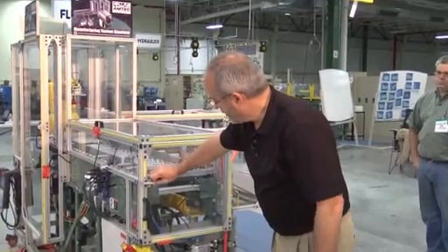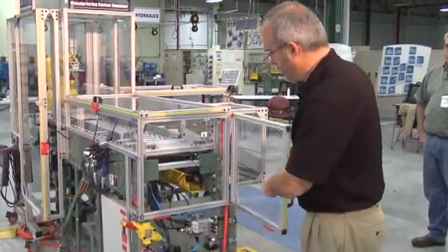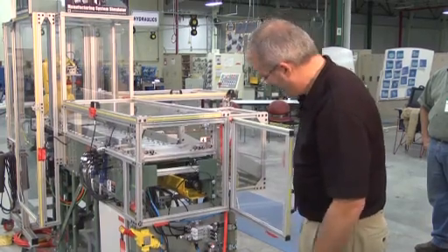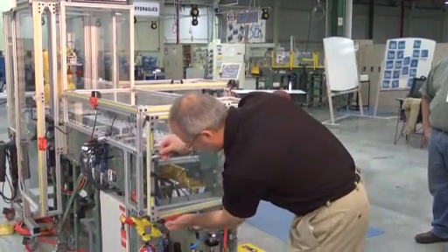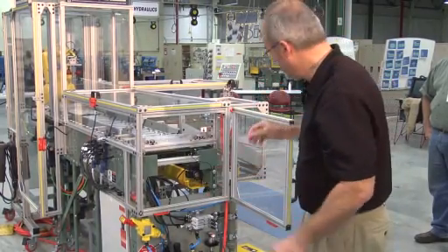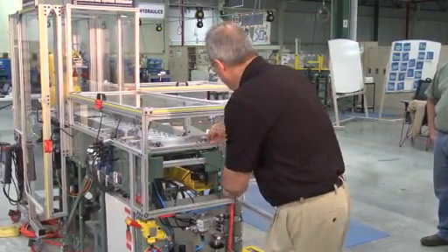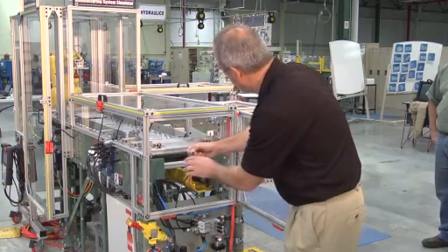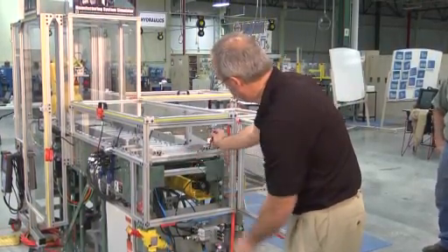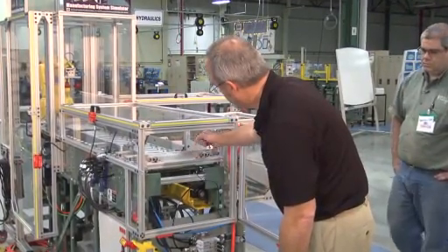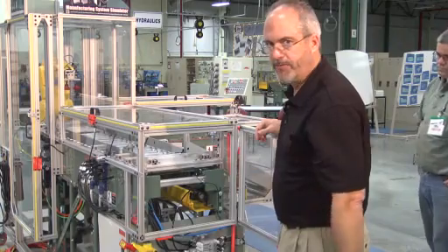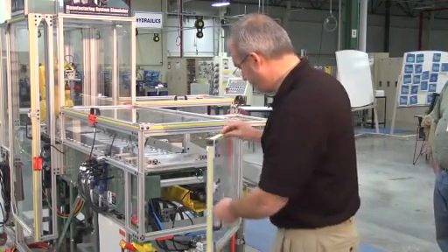Just like we had on the servo drive, and incidentally that was a demonstration here of another Estop. We have the gate interlock here. When I open the gate, the equipment Estops. But we have mechanical interference devices, just like we saw on the DC servo, that by simply moving these screws and placing them, we cause a mechanical interference, causing another fault scenario.